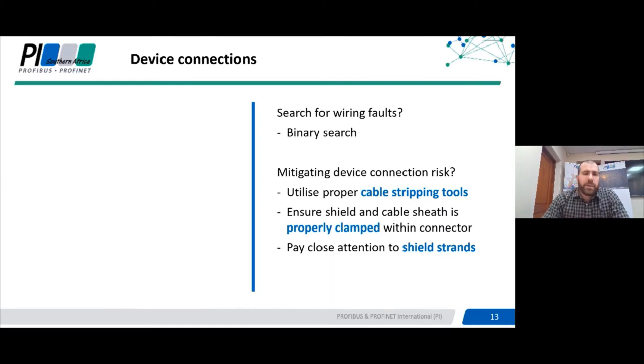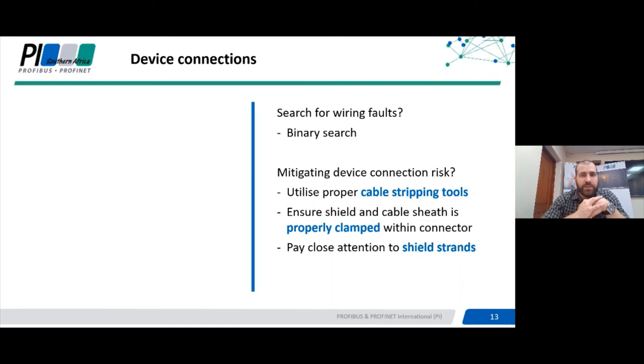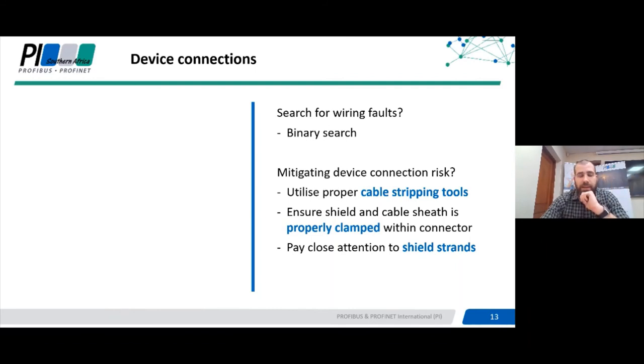To search for wiring related faults, use something called a binary search. A very useful feature built into Profibus is that all plugs have a termination switch which not only enables the termination circuit but also cuts off the outgoing line. So if you connect a bus monitor or oscilloscope and see a short circuit on the segment, simply move down the segment enabling terminations every so often until the fault goes away — the closer you get to where the fault disappears, the more you can identify which plug potentially has the wiring fault.